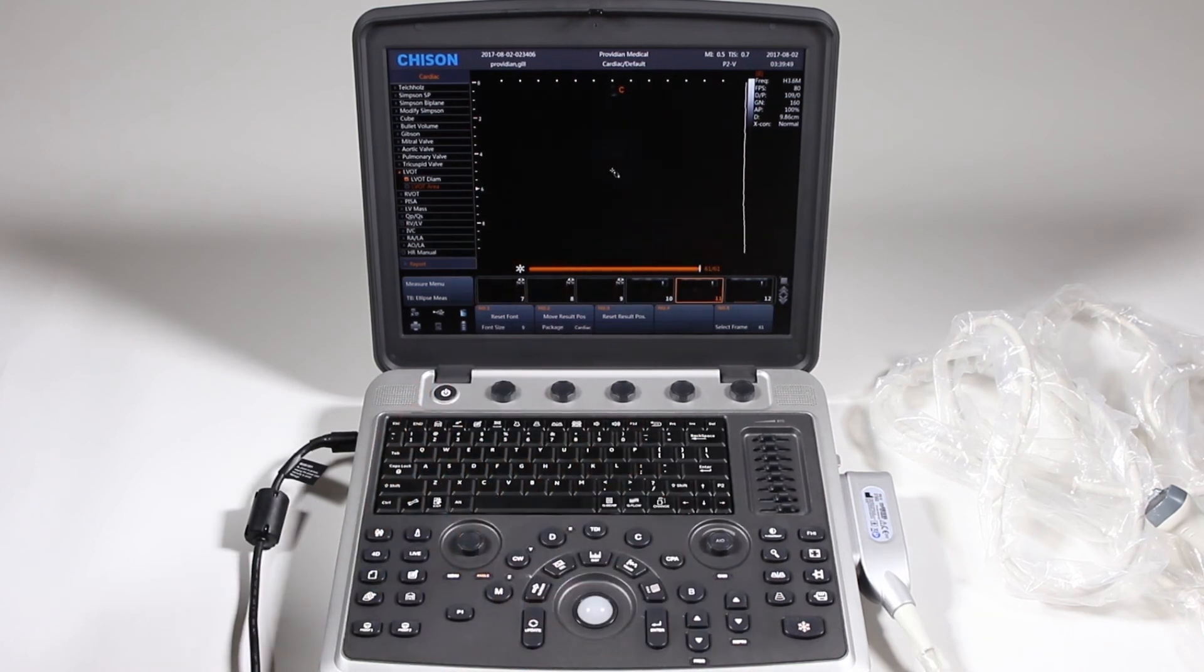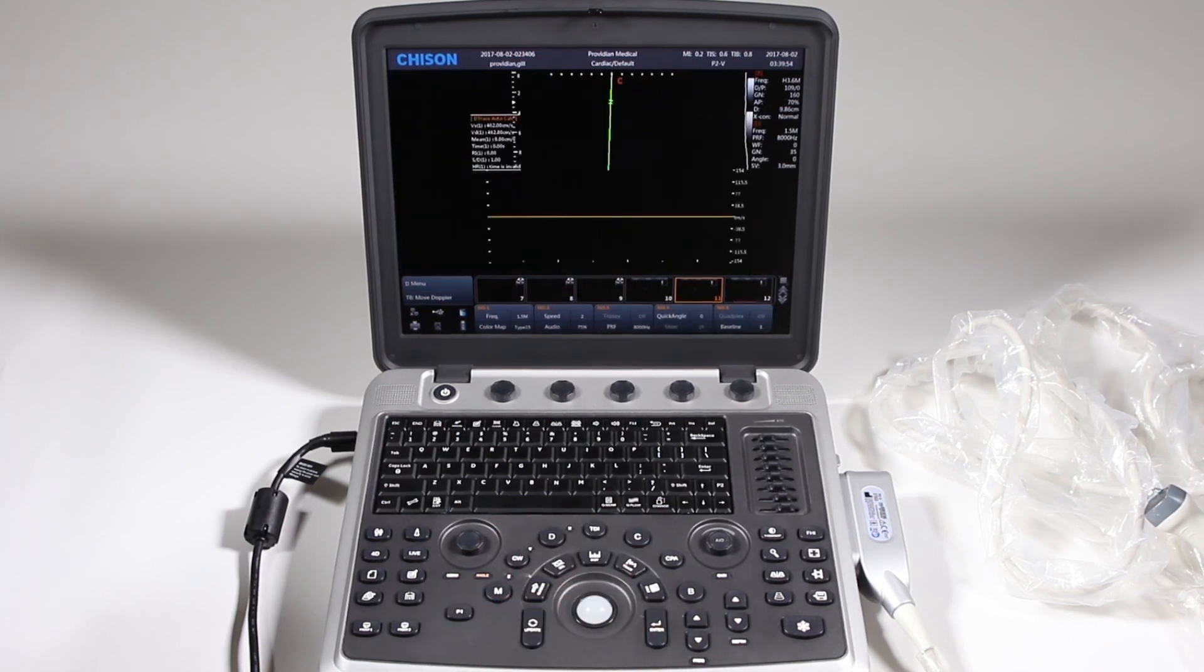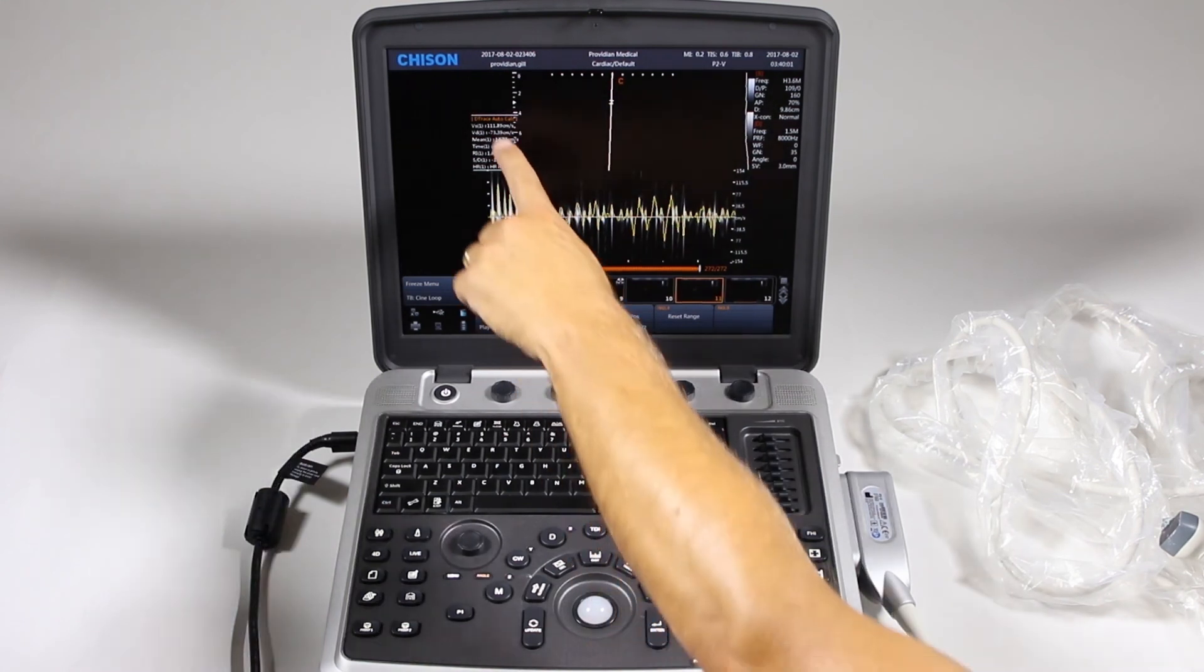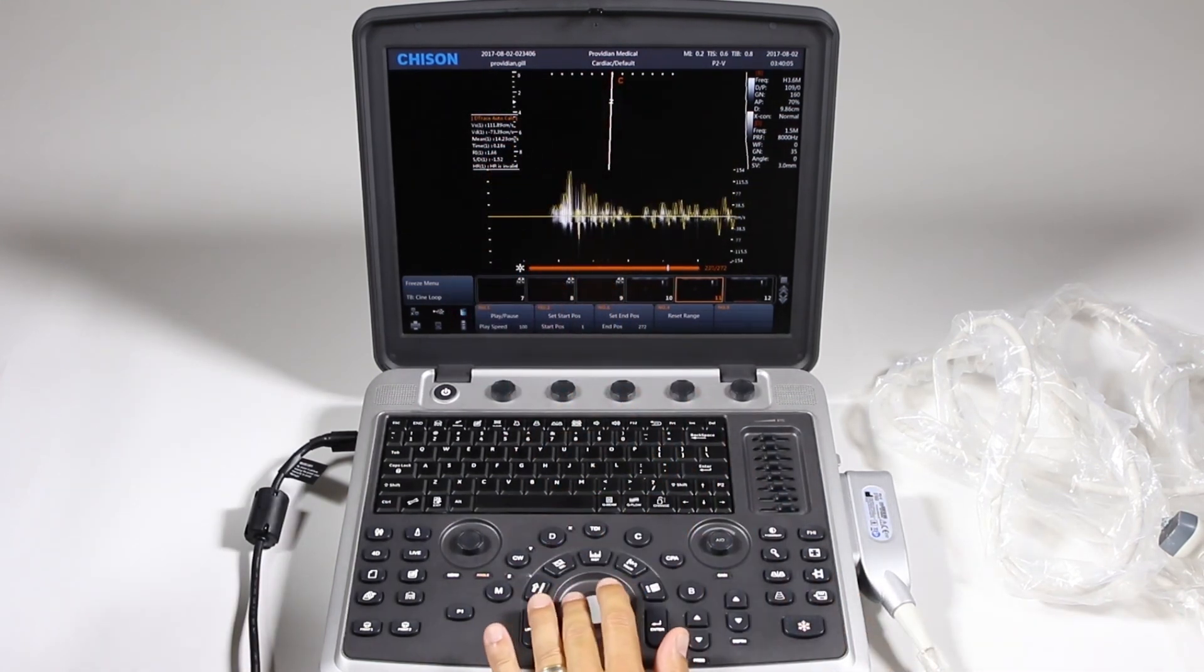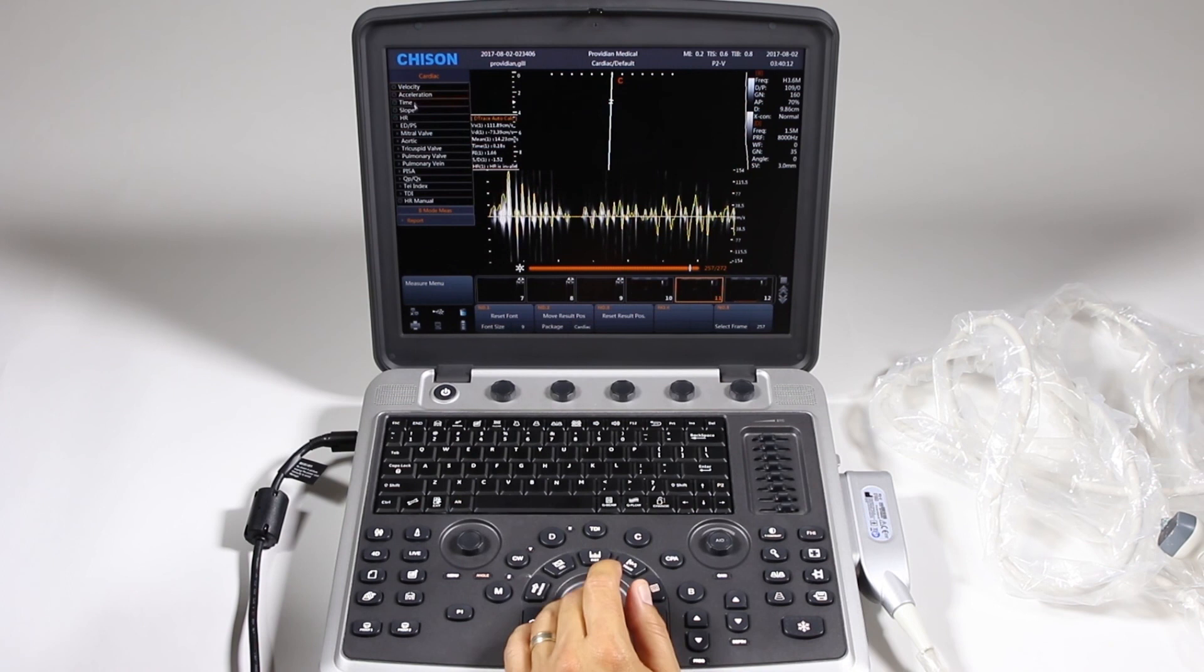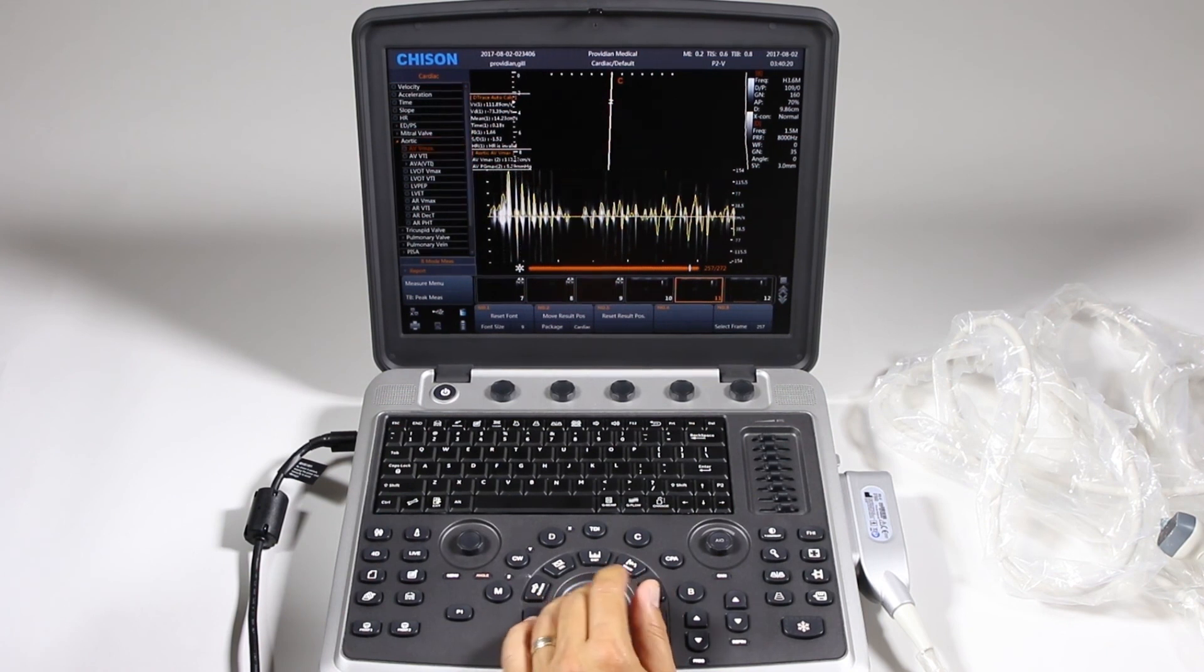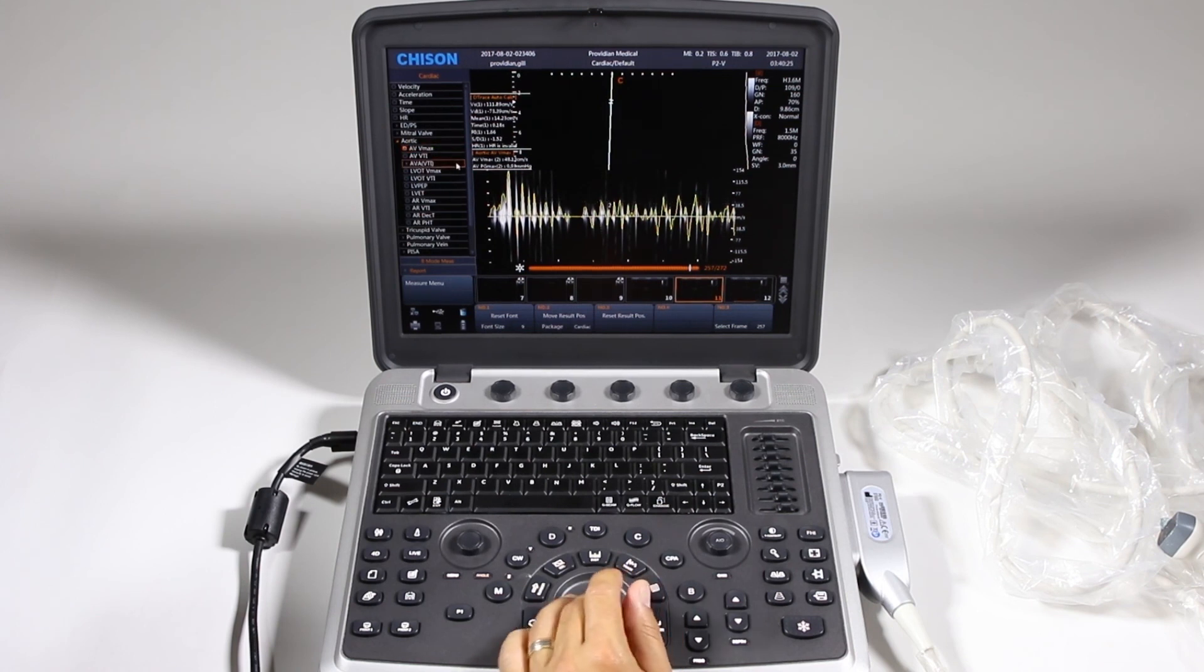And let's go into a Doppler calculation. So I'll just go into Doppler, click update. So we have the auto calcs on and freeze and this is showing my auto trace and the calculations. I can go ahead and hit calc and I can choose these various items here throughout there. And I can also make the measurements myself by clicking, I just click aortic velocity maximum, go ahead, hit set and I've got that saved right there.